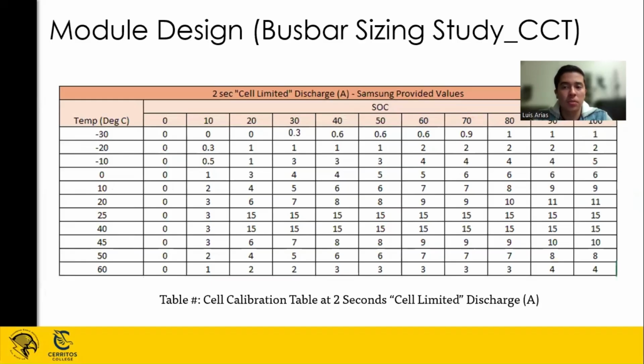We also want to check the minimum thickness using the cell calibration table. This data shows the cell-limited discharge rates for each cell at different temperatures and states of charge, and we see that 15 is the highest. We use this for the worst case scenario to determine the minimum safe cross-sectional area for the bus bars.